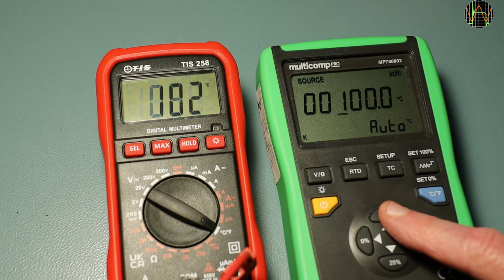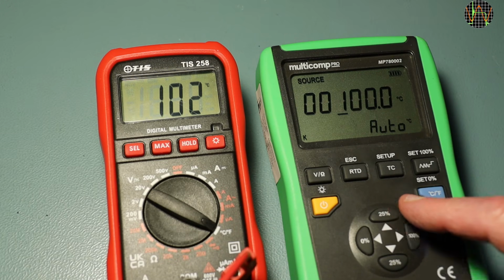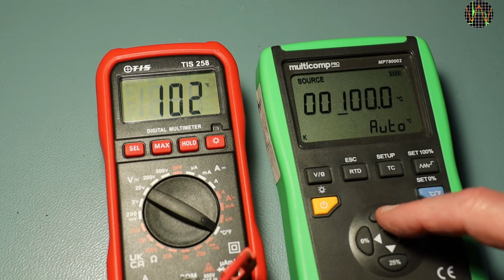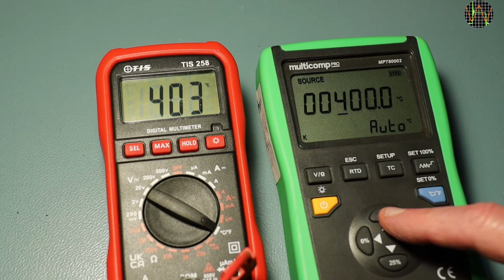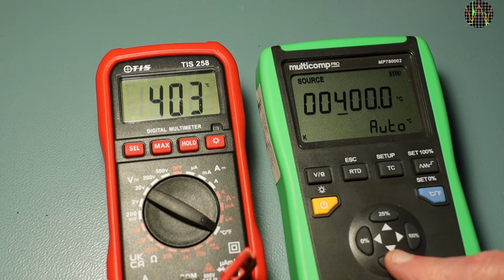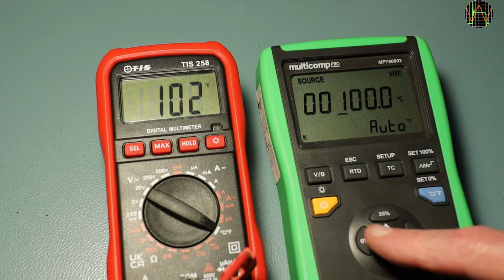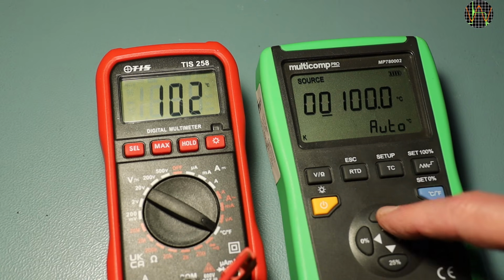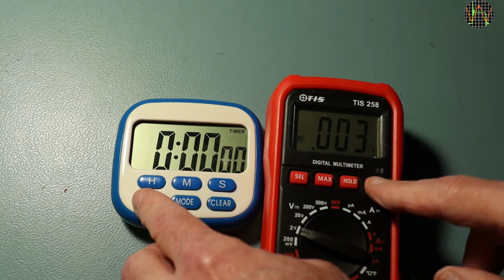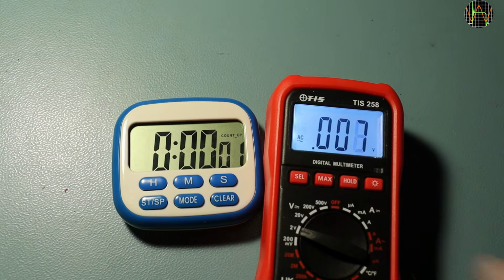For a quick test I connected a calibrator. It is set to 0 degrees Celsius and the meter shows 2 degrees. I could get more accurate results by entering the meter's cold junction temperature into the calibrator, but all I want to do is a quick functional test, entering a few simulated temperatures and seeing the meter shows about the right values. And it does. The backlight is quite bright, but short.